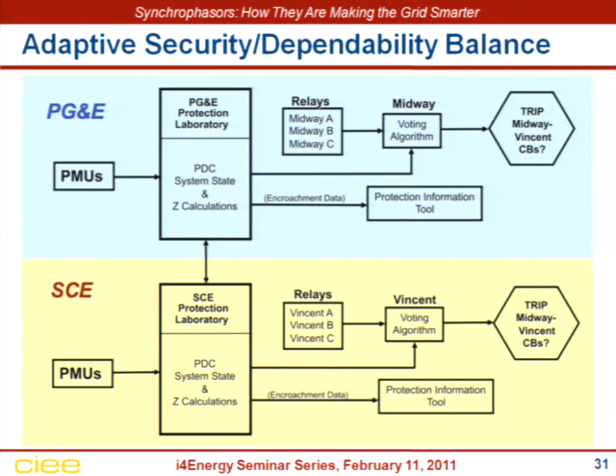They actually have protection system control centers that run all the special protection schemes for our part of the Western grid. These are things that take in wide area data, look at the health of the entire grid. They don't just look at individual lines. But the PMU data that we're monitoring in the field comes in, goes into these system state and impedance calculations, and it does two things.